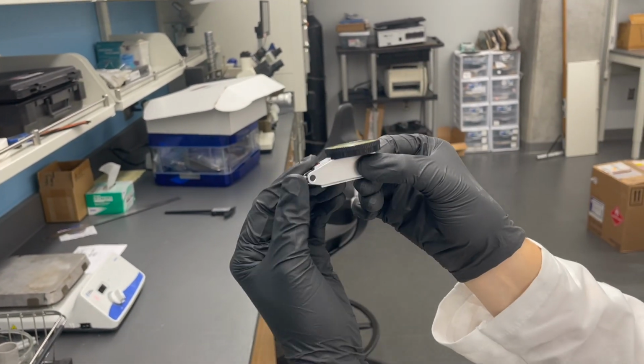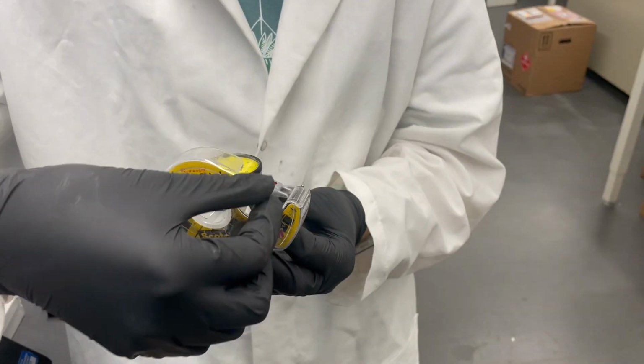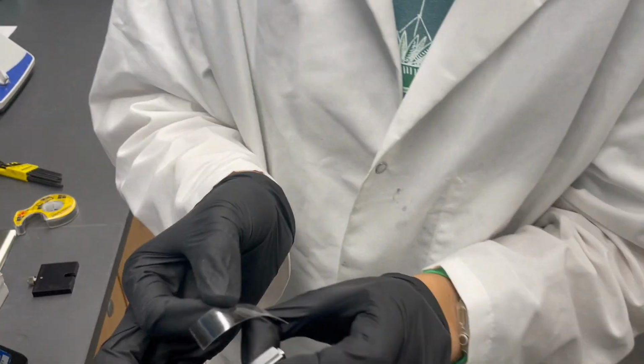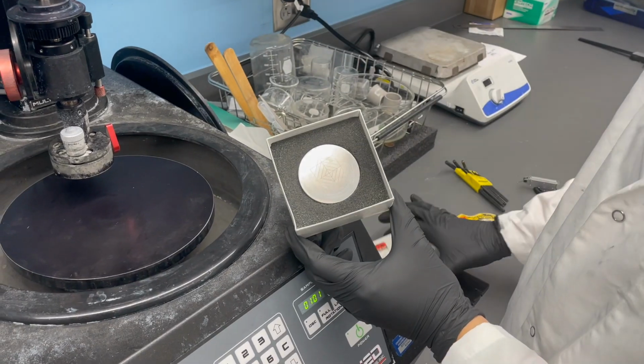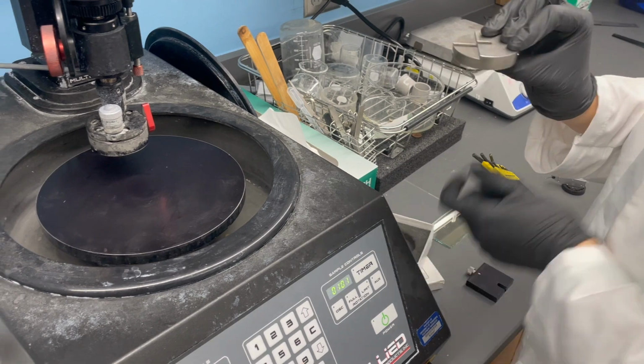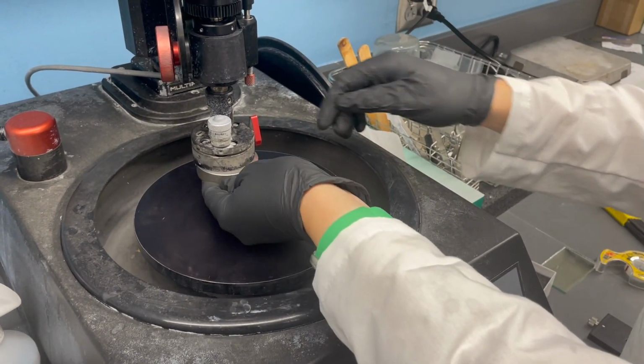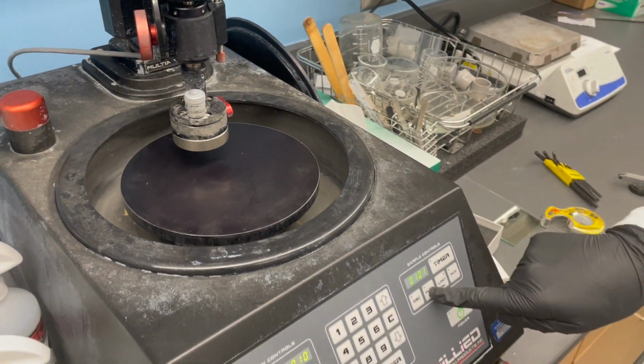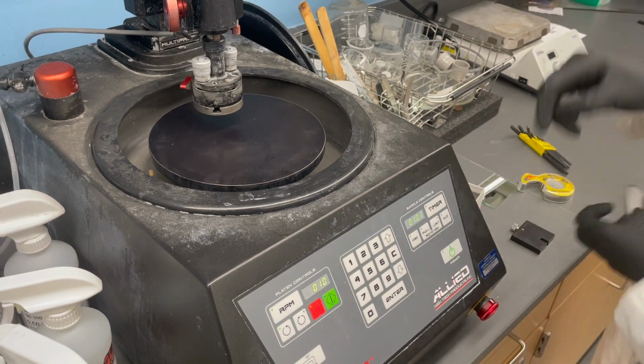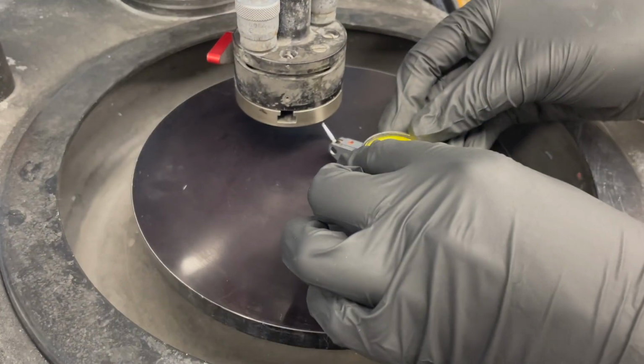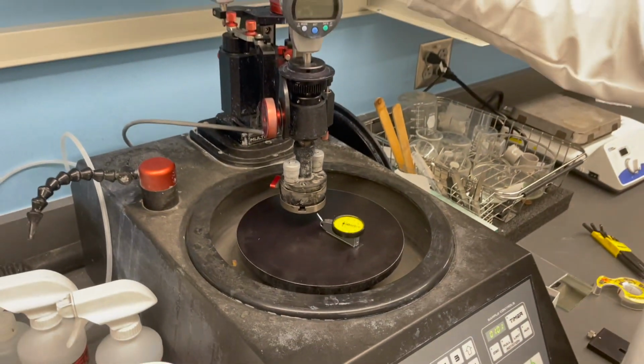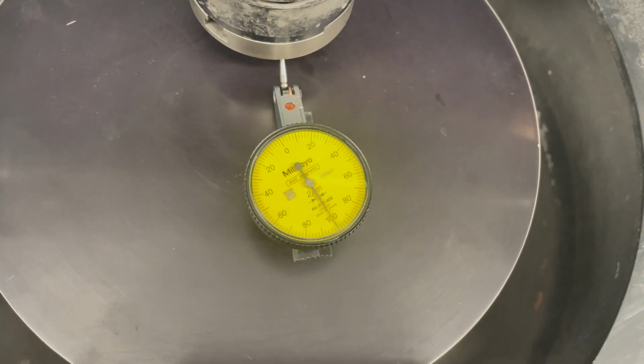Flip the dial arm so that it is pointing 45 degrees upwards. Then attach double-sided tape to the bottom of the dial. Take out the calibration polishing fixture and attach it to the head and tighten the red pin. Press the full button until the silver screw is at the 6 o'clock position. Align the screw with the dial arm and attach the dial on the platen where the arm is at the edge of the fixture. Lower the arm until the dial reads 0.